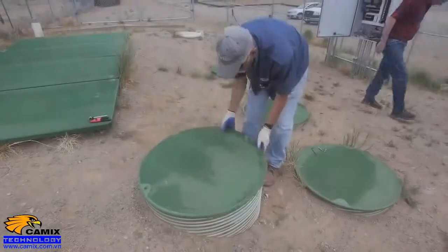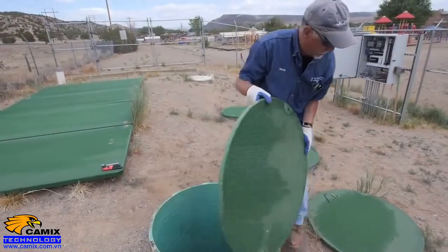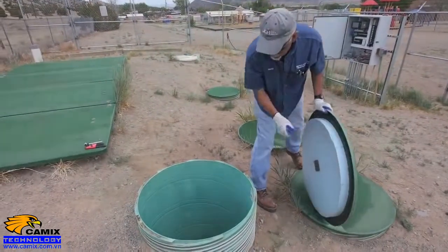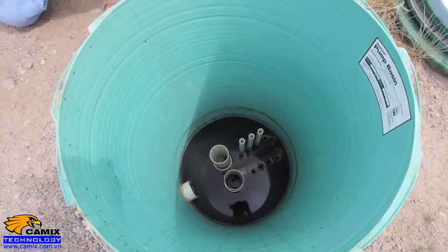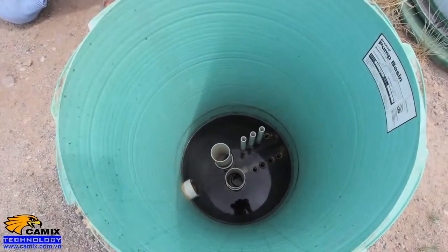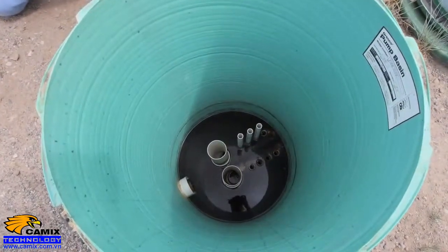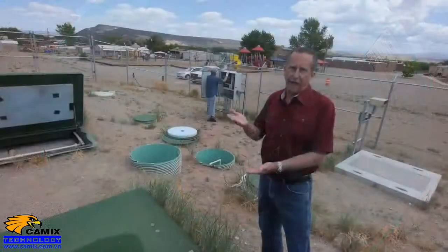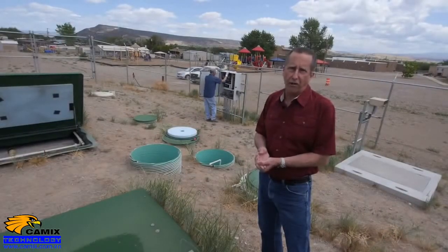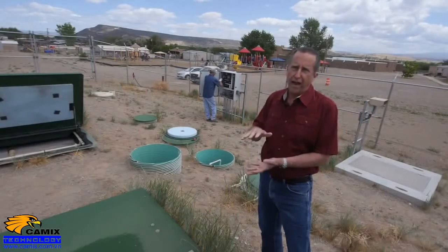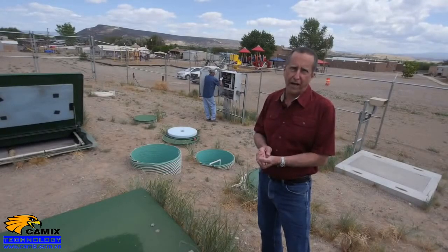Some of these on-site systems are a hybrid that utilize 2 or 3 different types of these processes in one package unit. Underneath the ground, under these circular covers, is sort of the first step in the process. You might call it primary treatment, but it's a combination of primary and preliminary treatment because there's basically just a 20,000 gallon baffled tank. Anything that can settle out of the raw sewage will settle. Anything that can float, like oils and greases, will float. Any kind of trash can be separated out.